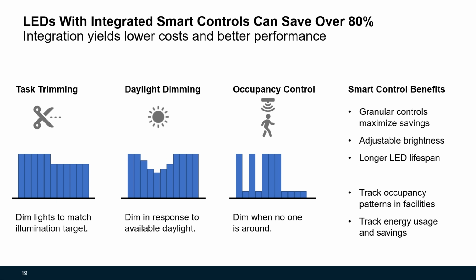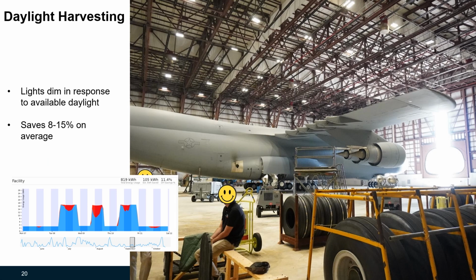In one example, for daylight harvesting, this is a picture of the hangar with the bay doors slightly open. You can see that as the doors open, you get some savings in the graph. The red indicates the amount of energy you save due to daylight harvesting. Here we saved between 8 and 15% on average throughout the year, depending on the facility. And the facilities we had did not have a whole lot of access to daylight.